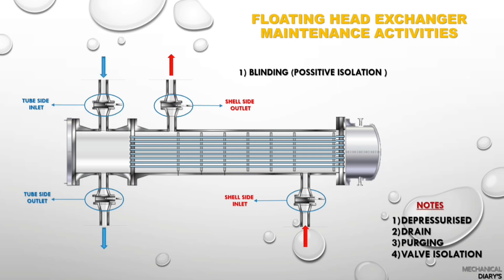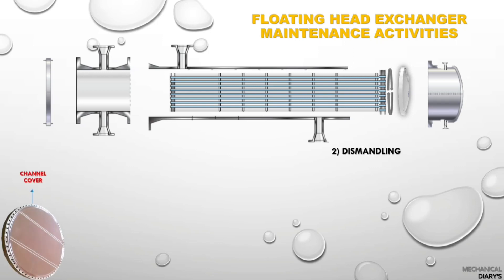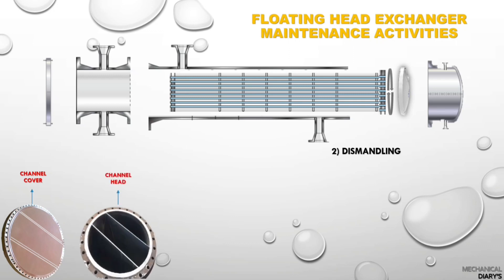Blinding is one of the most important and dangerous activities, so you must follow all safety rules and regulations. After blinding, we have to make sure the exchanger has been flushed, purged, and confirmed safe. Then we can go for dismantling. During dismantling, you should mark each and every part — this will help you when boxing up the exchanger.